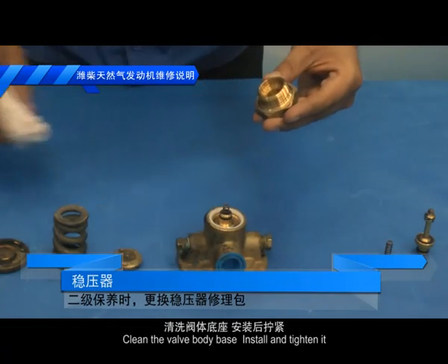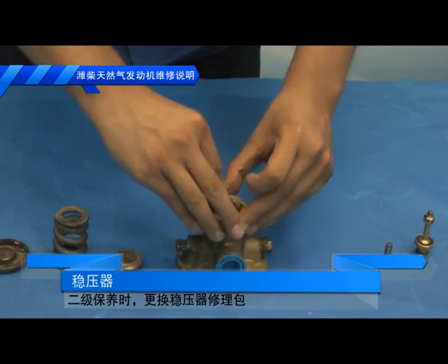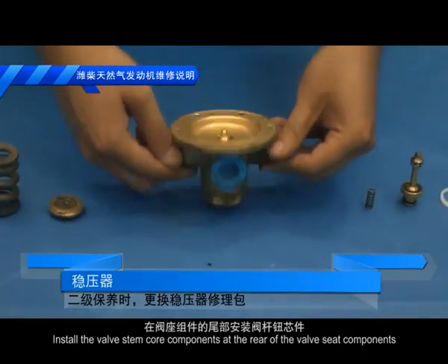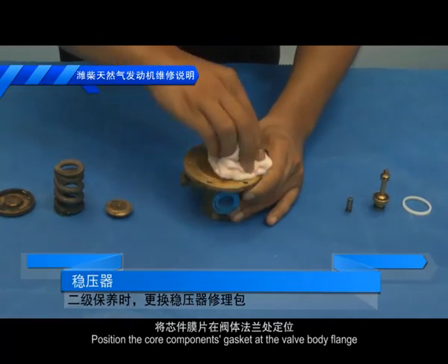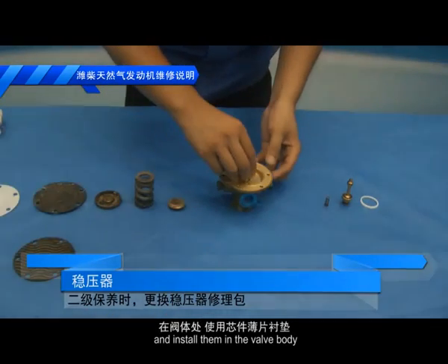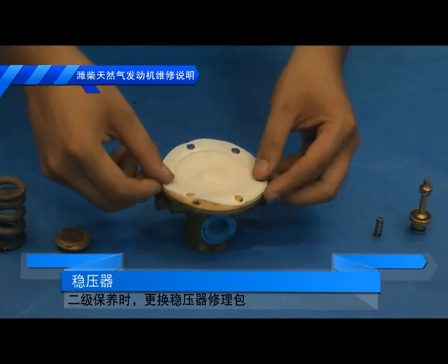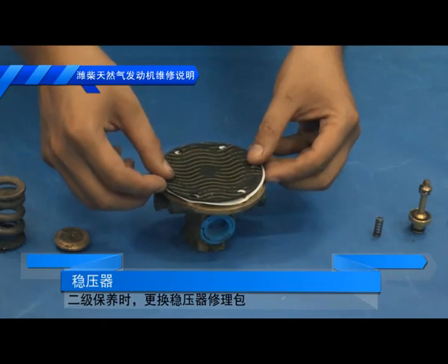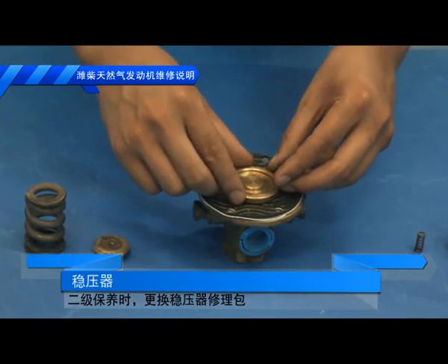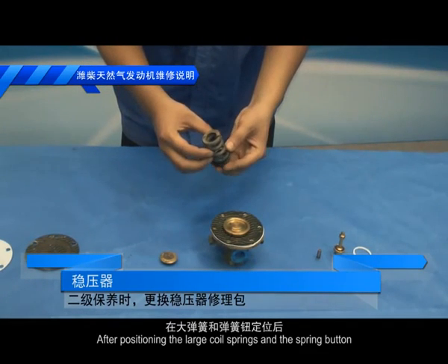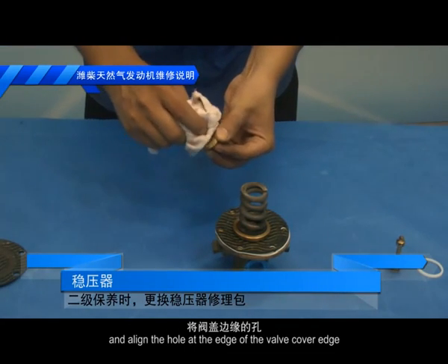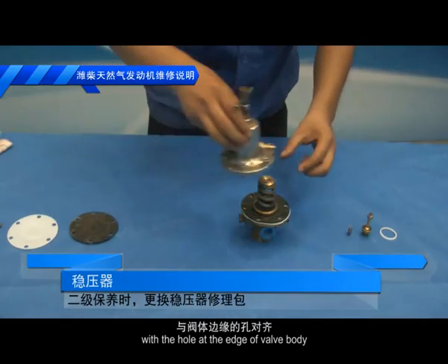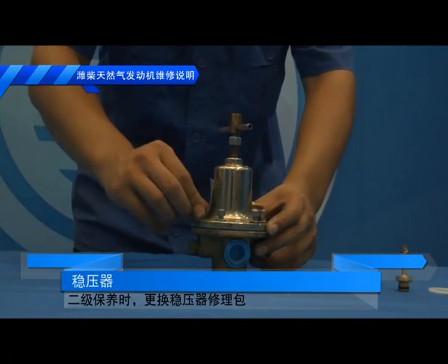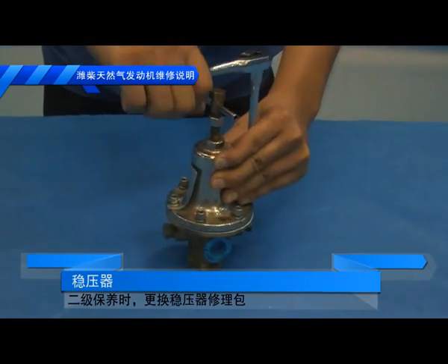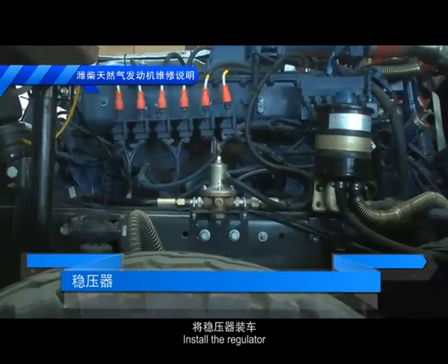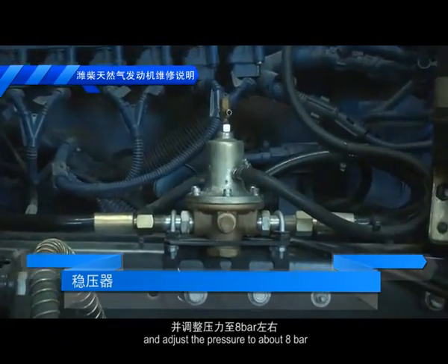Clean the valve body base, install and tighten it. Install the valve stem core components at the rear of the valve seat components. Position the core components gasket at the valve body flange and install them in the valve body. After positioning the large coil springs and the spring button, adjust the gasket plate to the center of the gasket and align the hole at the edge of the valve cover with the hole at the edge of the valve body. Insert screws and tighten them. Install the regulator. Test for air leakage under idling condition and adjust the pressure to about 8 bar.